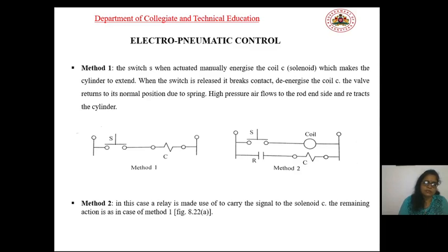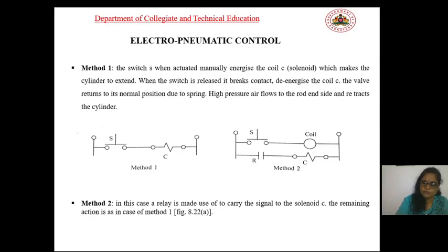High-pressure air flows to the rod side of the cylinder and retracts it. When it comes to Method 2, as observed from Figure 2, a relay is used to carry the signal to the solenoid C. The remaining action is the same as in Method 1.